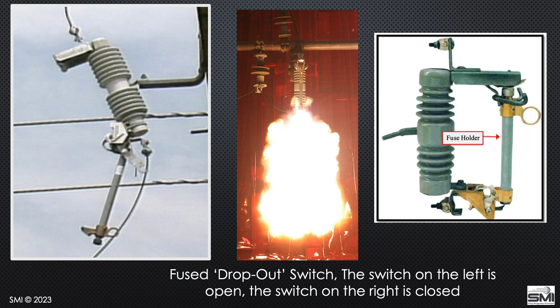I try to let them know that even if the cutout is blown and the cutout door is hanging down, it doesn't mean the line is de-energized. The only way to know it's de-energized is to use a Bierer meter and get it tested. There are times when an event like trees on the line may still be in contact above the cutout, so it might still be energized.